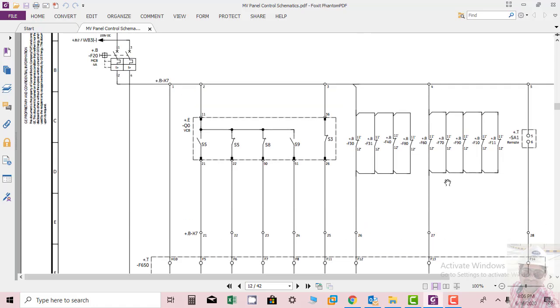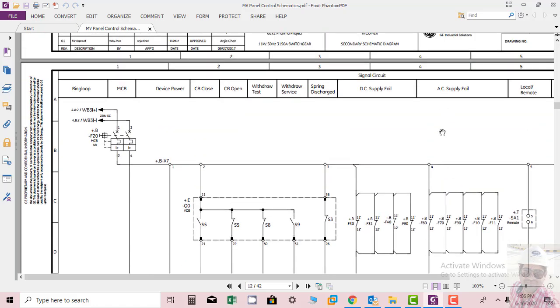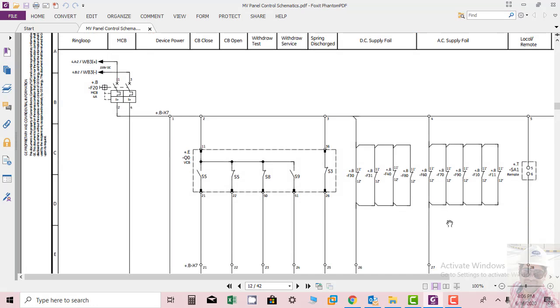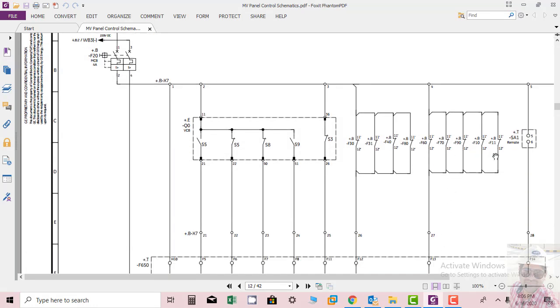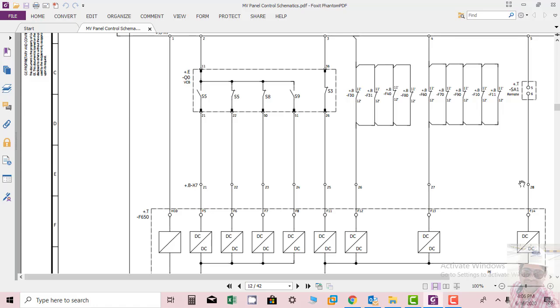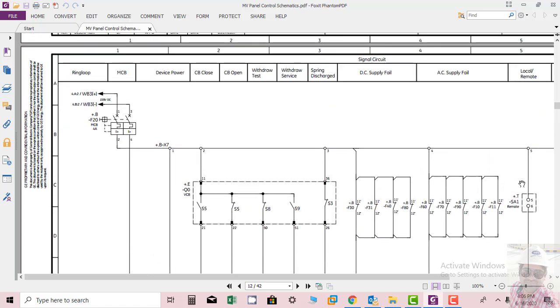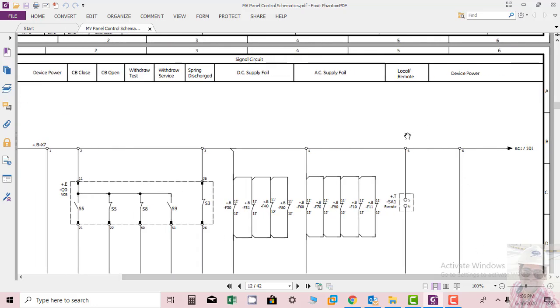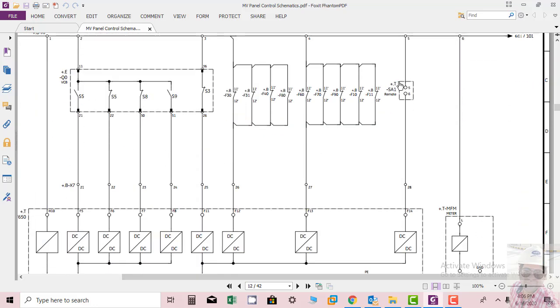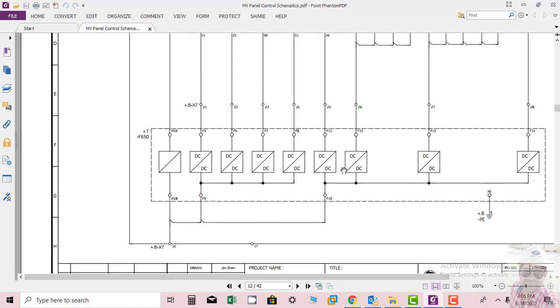Similarly, here you can see AC supply fail. Normally closed contact of MCBs are wired up here, and it is connected to binary input. Again, you can see the local remote selection. Also, one contact is connected to binary input. So this is all signaling. So move to the next sheet.